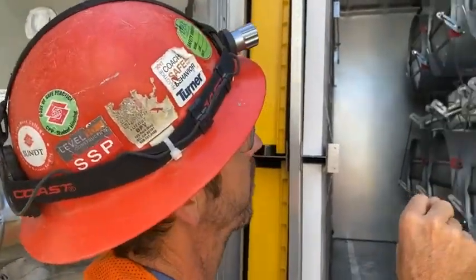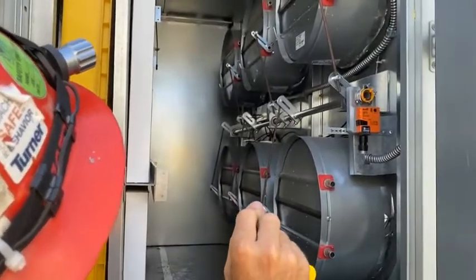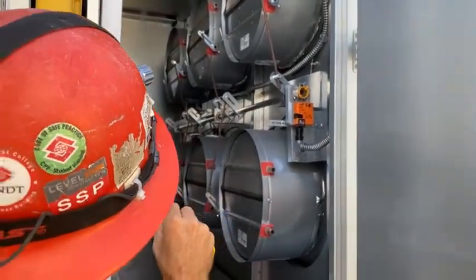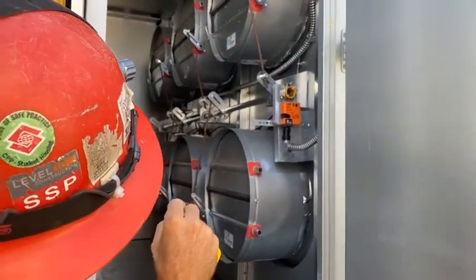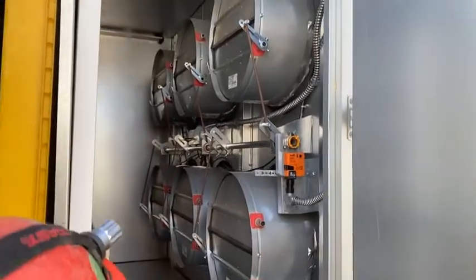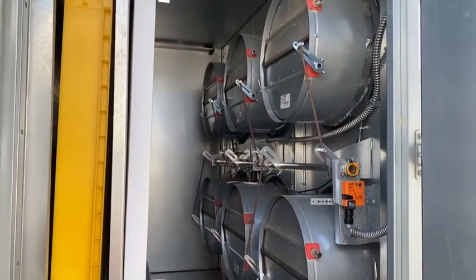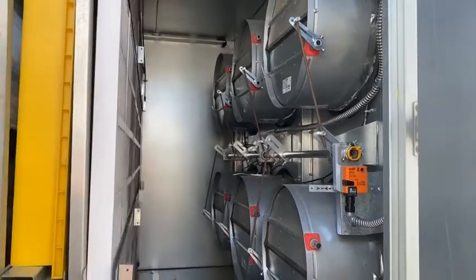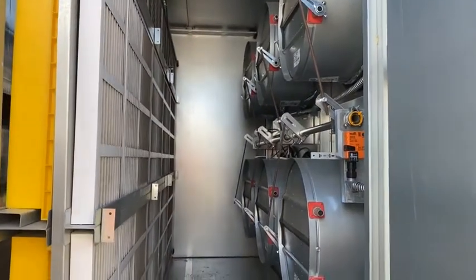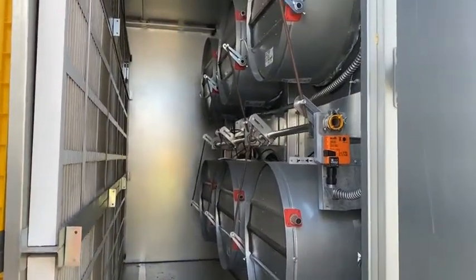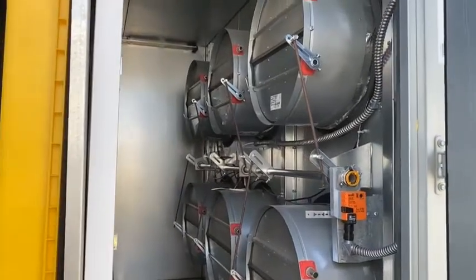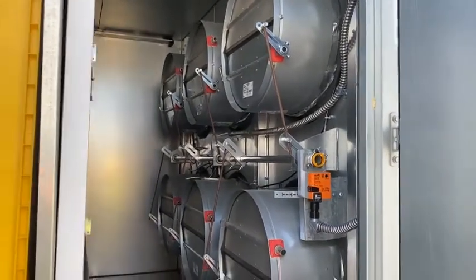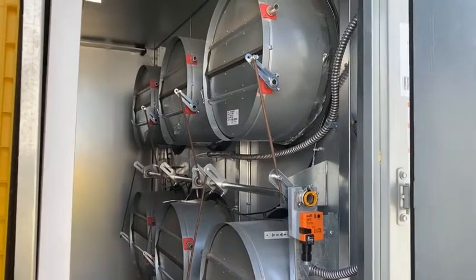The control guys will open this damper right here. They're all linked together, okay? All this rod right here, there's linkages that tie all these together. I would inspect those quarterly. If the unit's not running, they'll be closed. You just want to make sure there's no binding. All the lips here should be touching when they're closed.